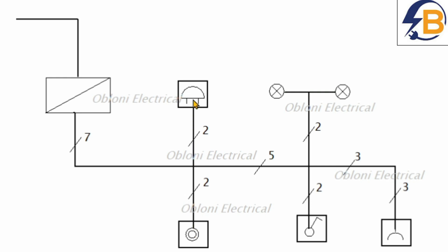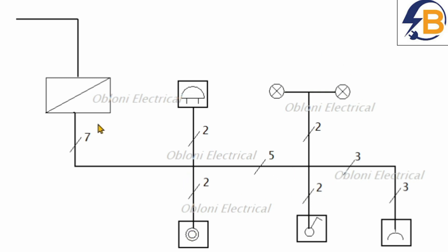The remaining four — where are they going? We know we must have a feed supplied to the bell switch and another feed supplied to the one-gang switch. In this drawing, what is shown means we have one feed and then another wire to the bell. If the cables here are only two and we also have two here, this simply means we are taking two separate feeds from the consumer unit — one feed to the bell switch and another feed to the switch.